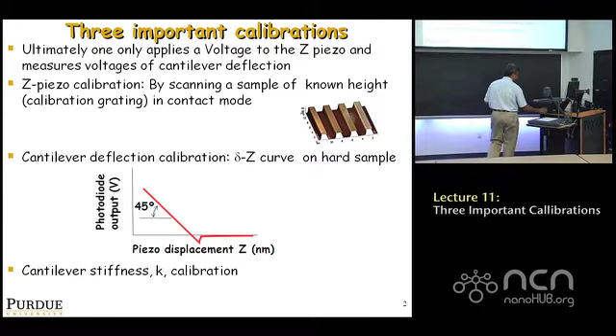For the Z-piezo calibration, what you need to do is buy what are called calibration gratings. There are many suppliers of AFM calibration gratings, and many kinds. There are some designed mostly for calibrating the Z-piezo, like the one on the left. There are some, like in the middle, designed for calibrating all three piezos, X, Y, and Z. And then there are some, like on the right, designed for calibrating things related to friction force microscopy, like if you want to know what angle you're twisting by and so on. So you can buy these, and all of you should have them if you do atomic force microscopy. The idea of these gratings is the following. They have known dimensions, right?